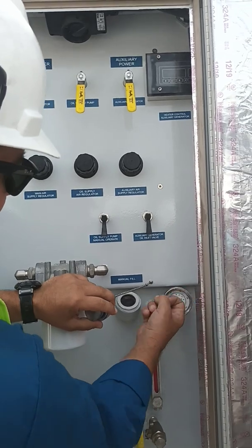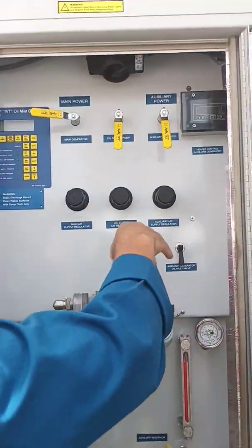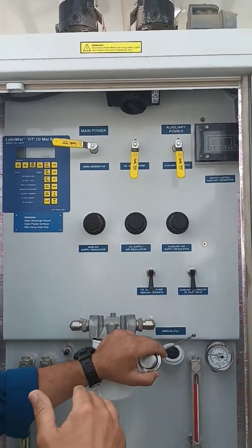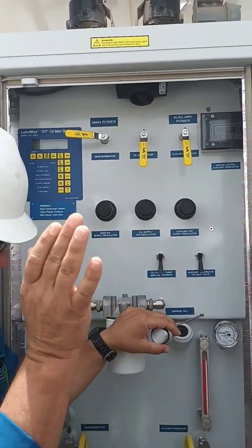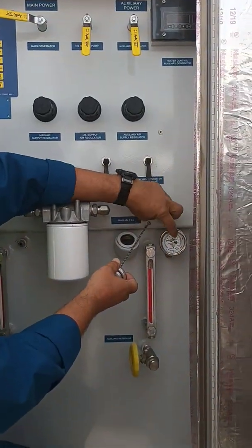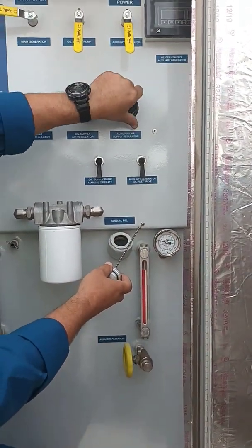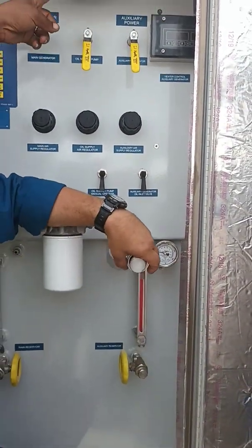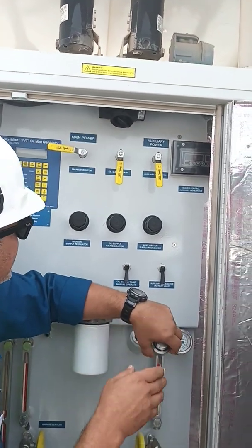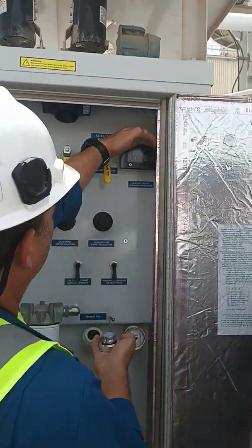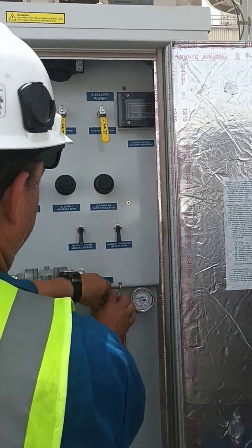But this one is running now. When you run the auxiliary, you can put the power to the auxiliary now. The air heater will go up to 49 degrees C. That's it. But the most important thing is the 20 inches here. Just put the power. 20, 22, no problem. We just have to rotate this one. Yeah, that's it, you can see it here. Now it's already 40. You don't need to press any button. All you need to do is make sure that you have 20 here. 20 inches, which is 50 millibar.